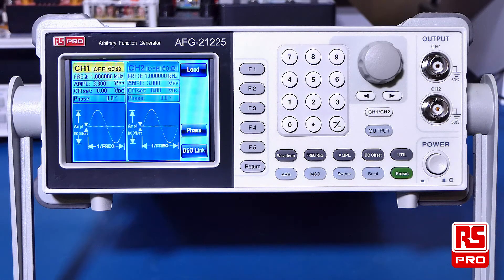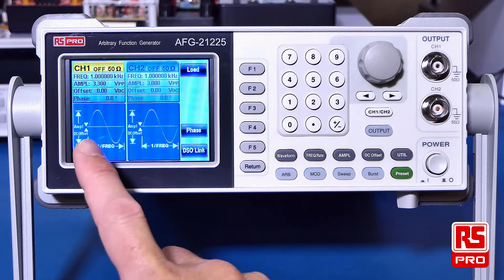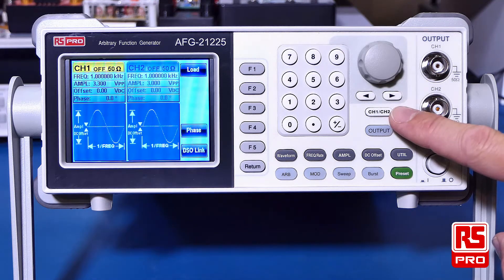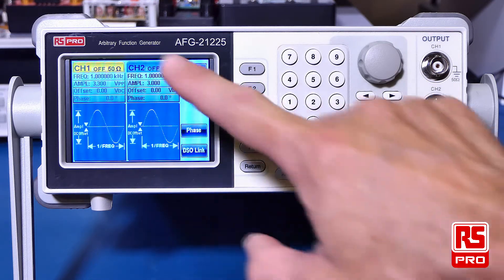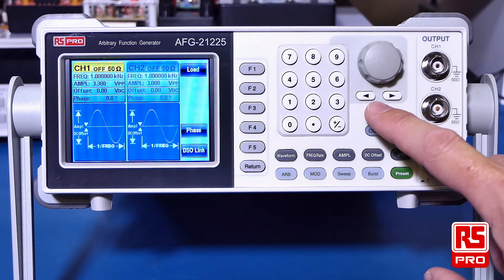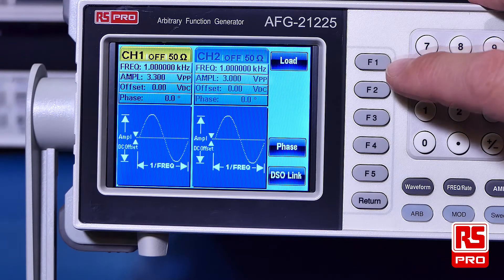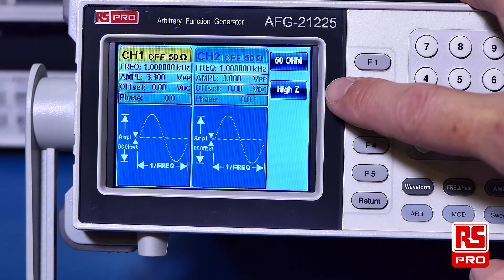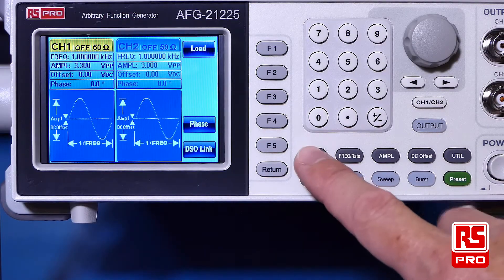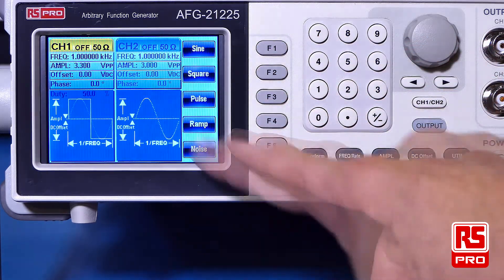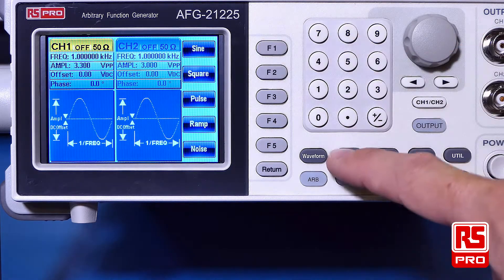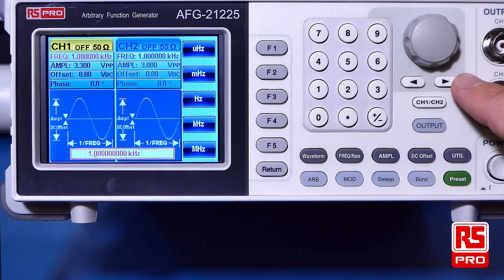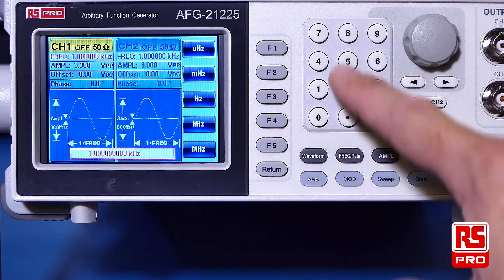The RS-PRO AFG21225 function generator provides an easy parameter entry for both channels. Channel 1 is set on the left hand side and channel 2 is set on the right. You can use the channel 1 or channel 2 button to switch between the two channels to set your various parameters. The load or impedance of your channel can be set with the soft menu function 1, where you can select between 50 ohm or high impedance. Using the waveform button you can select the type of waveform — in this case we'll set the sine wave. We can set the frequency rate; we'll set 5MHz.